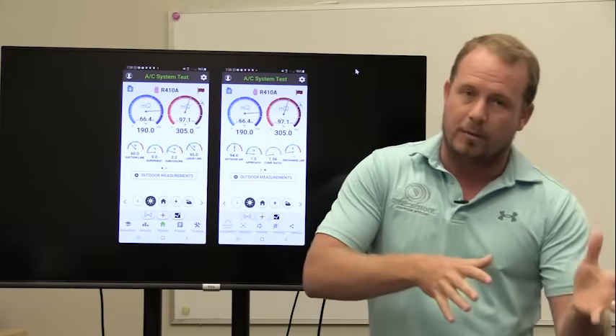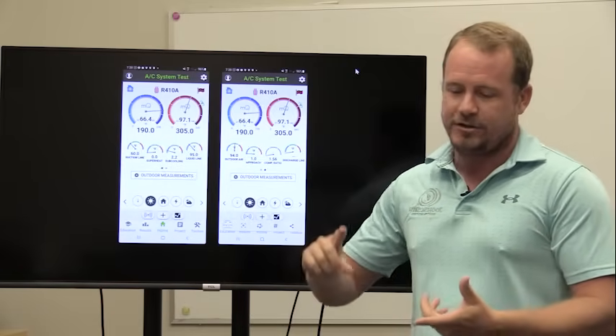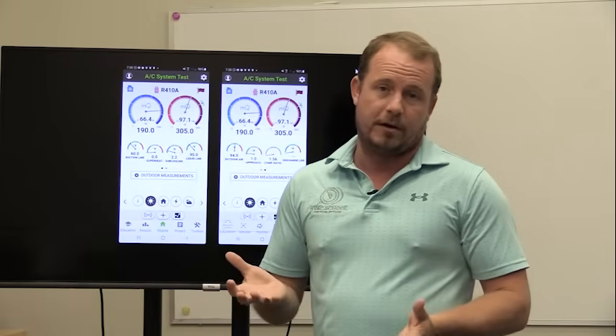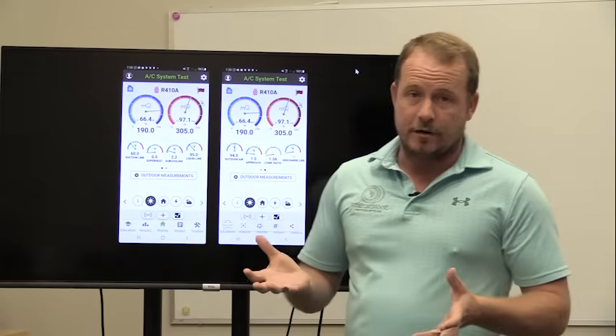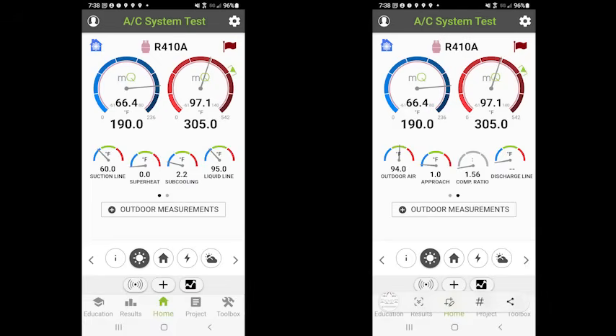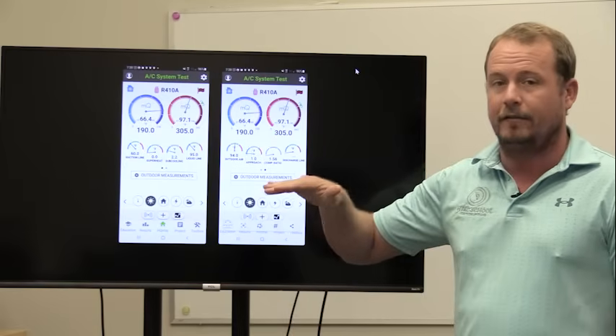So you wouldn't want to have another problem that caused the compressor to do this. You replace the compressor and now you have the exact same thing. You want to eliminate through process of elimination, eliminate the reversing valve, eliminate every other possibility before you replace a compressor that's not pumping. But what you're going to see in your measurements is going to be the same. It really comes down to compression ratio and current. But what you're going to notice first generally is going to be abnormally high suction. Keep in mind if it's in hot pull down because you have a really warm space, that would be expected. You're going to have low head pressure. So you're going to have a CTOA that's very low. In this case, we're showing 97 degrees and outdoor air temperature of 94. So that's very low.